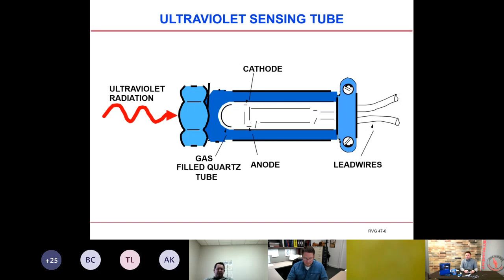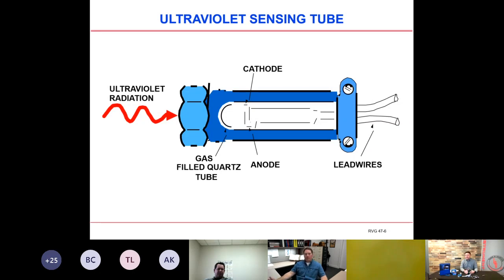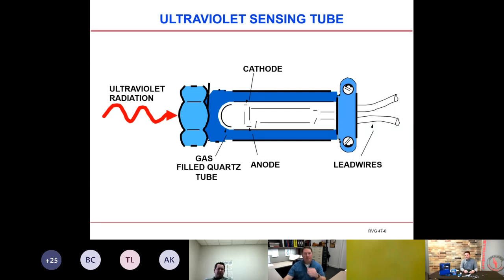All UV sensing tubes in the industry can fail in the unsafe condition — meaning they can fail in the ionized state. The only time the UV tube performs a self-check is when you shut down the flame relay and restart it, known as a safe start check. This checks to make sure the tube is not firing when it shouldn't be. For applications using a single tube like this, with no continuous self-checking, you must shut down at least once every 24 hours to make sure you don't have a runaway tube.